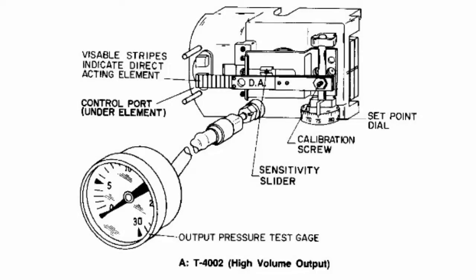I wanted to stop and clarify something about thermostat calibration before we moved on here. When your room temperature and set point dial are the same values, let's say 72 degrees, you're going to be sending an 8 psi control signal to a control device. There's a sensitivity slider screw that should never be adjusted on these, and that's highlighted here. If this gets adjusted, you can completely screw up how your thermostat works.